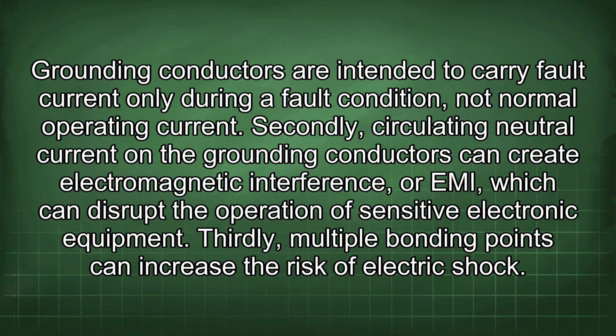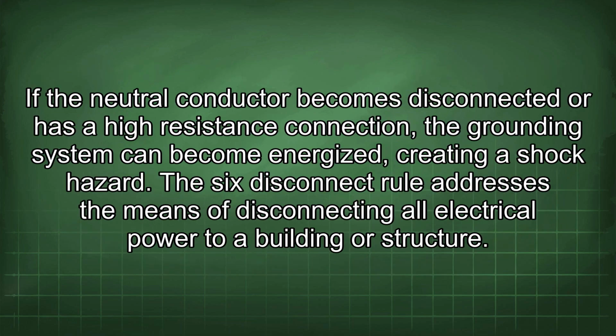Secondly, circulating neutral current on the grounding conductors can create electromagnetic interference, or EMI, which can disrupt the operation of sensitive electronic equipment. Thirdly, multiple bonding points can increase the risk of electric shock. If the neutral conductor becomes disconnected or has a high resistance connection, the grounding system can become energized, creating a shock hazard. The 6 disconnect rule addresses the means of disconnecting all electrical power to a building or structure.